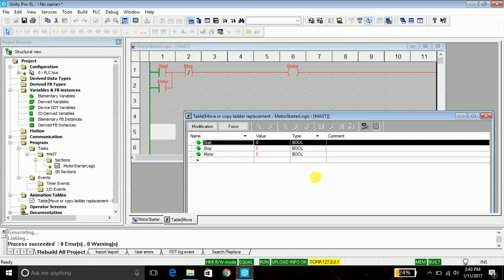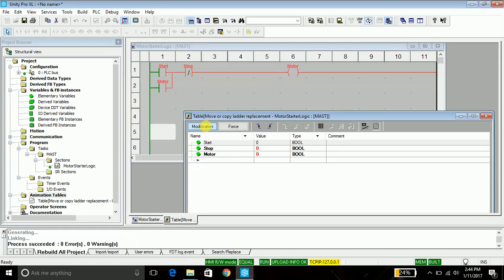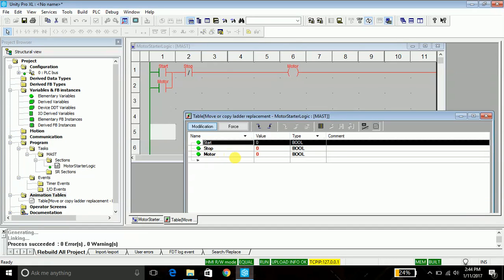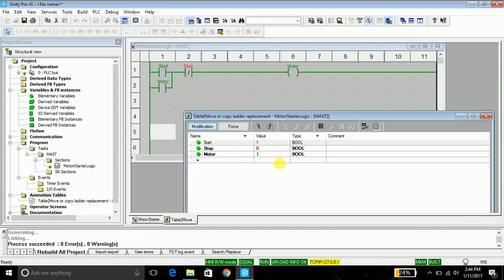So in order to simulate the working of the start button, we need to first highlight the modification tab. As my data type of the variable is boolean, if it is extended boolean then I will select the force, but since it is boolean I will select the modification tab. Then highlight start button, set its value to 1.